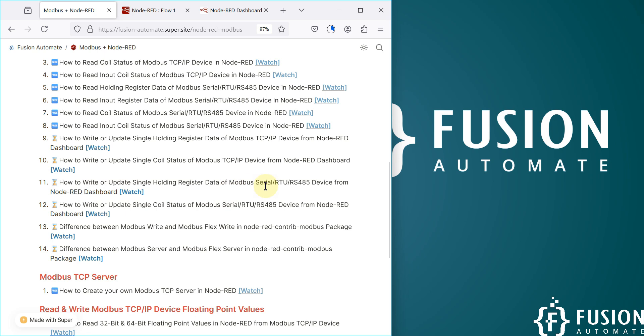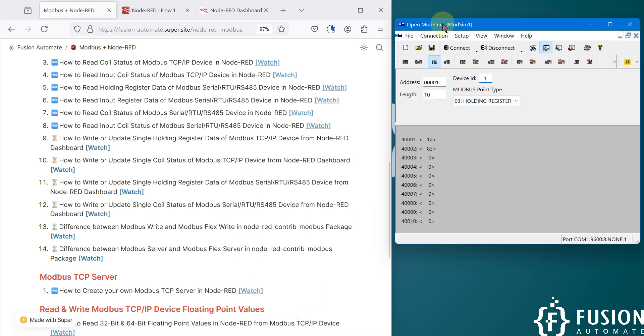If you don't have a Modbus serial device, you can use the OpenModSim software to simulate your Modbus serial device. I am using OpenModSim and simulating my Modbus serial device on COM1 port with 9600 baud rate, data bits 8, parity none, and stop bit 1.